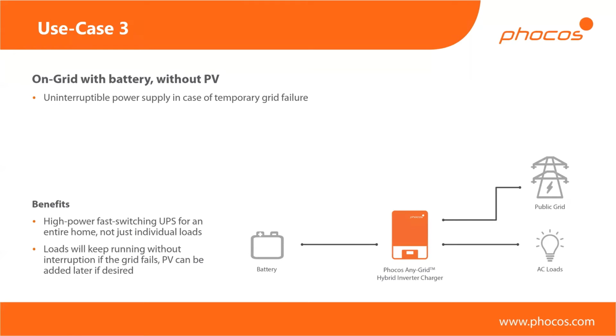So in this case, you benefit from the fast switching between the grid and off-grid modes, and you can be sure that your home is still running even if the grid fails. Obviously, in this scenario, because you have the public grid as your only energy source, the system is only as good as your battery. So when the battery capacity is depleted, then at some point the inverter will have to turn off. But it's definitely good to keep you running for probably several hours, even if the grid does fail.